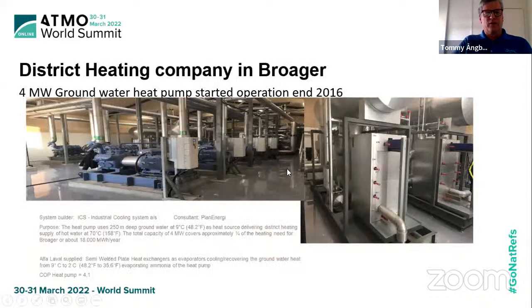Another district heating company installed a 4 megawatt groundwater heat pump, and it's been running quite well since 2016 already. But they use 250-meter deep groundwater at 9 degrees, so it's 48 degrees Fahrenheit, as heat source, delivering district heating supply water at 70 degrees. That means it's delivering a total of 18,000 megawatt hours per year of heating. And Alfa Laval supplied semi-welded plate exchangers as ammonia evaporators, cooling the groundwater from 9 to 2 degrees, evaporating ammonia.